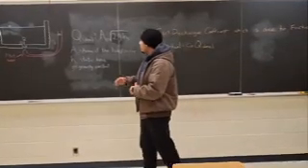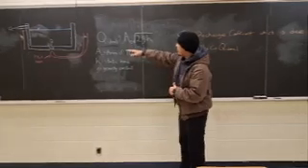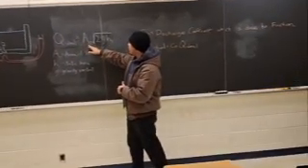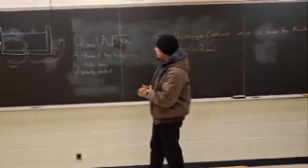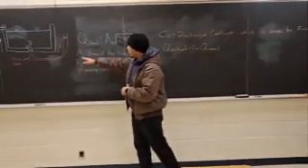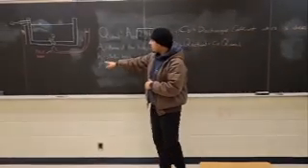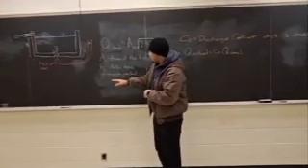Alright, so now we're going to focus on how to calculate the flow. As you can see here, we have an equation. Q ideal is equal to A naught times the square root of 2 times g times Hs. Down here, we know that A naught is the area of the hole of the orifice, Hs is the static head, and g is the gravity constant.